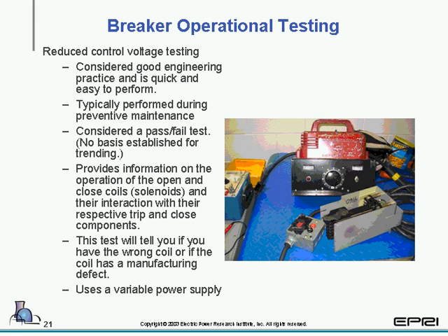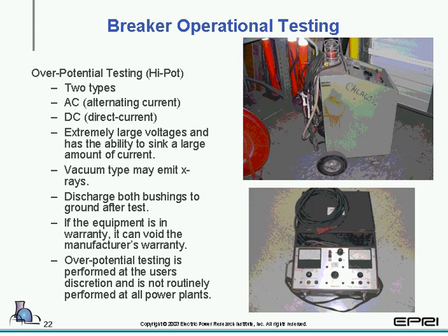Reduced control voltage testing, as we spoke about with the X and the Y, one of the items that comes in very handy is this particular picture, which shows a rig that can be mobile for operating a breaker from anywhere. It can be brought out to the cubicle and can be used to open and close and check anti-pump. That's a fairly simple setup. Most power plants would like to have this type of equipment in their plant.